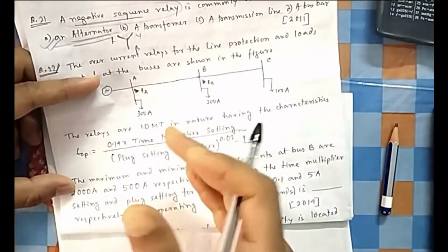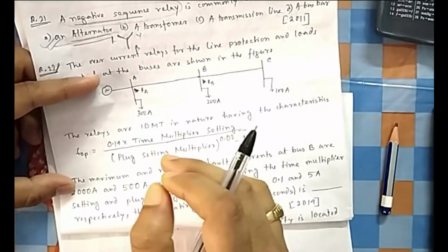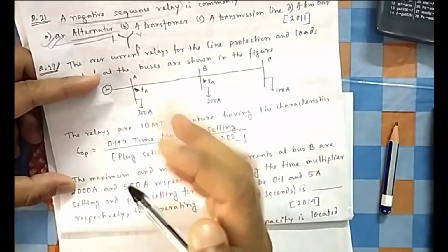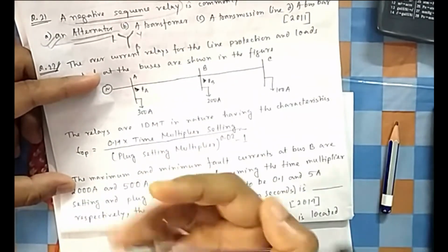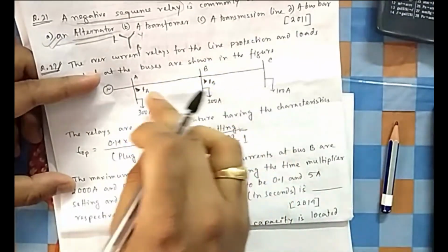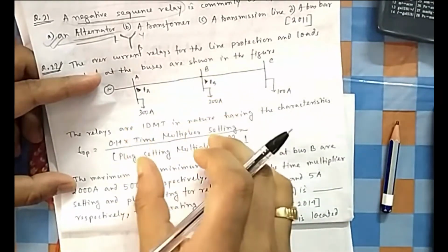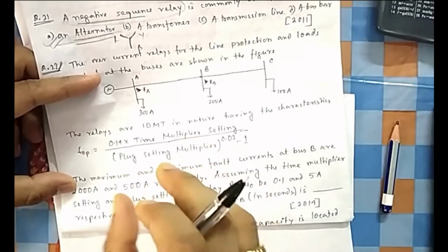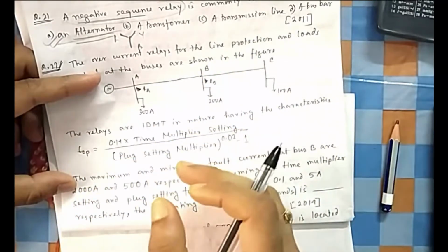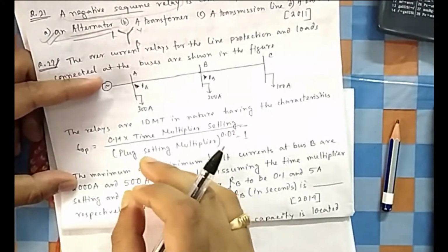The coordination exercise starts with the minimum time, a very fast response, when the situation is very problematic and within a fraction the system is working. If in that case the coordination can be maintained, meaning the backup will wait until the primary trips, then it is likely that it will also work when the time taken is more. So I have to think of the fastest case.